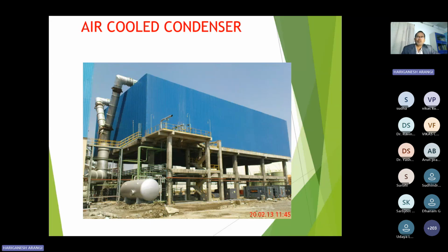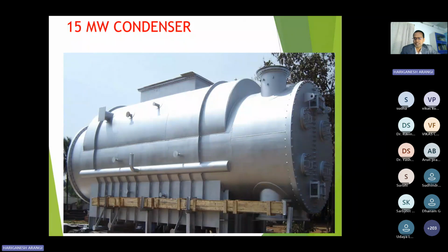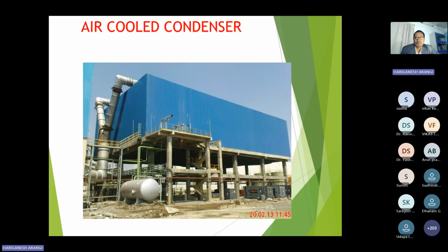In most plants where water scarcity is there, people use an air-cooled condenser, where we don't require any water to cool the low temperature steam and get the water. So this is the air-cooled condenser. Earlier, what we have seen was the water-cooled condenser. There will be a cooling tower, and in that cooling tower, water comes to this condenser. So equipment also increases.